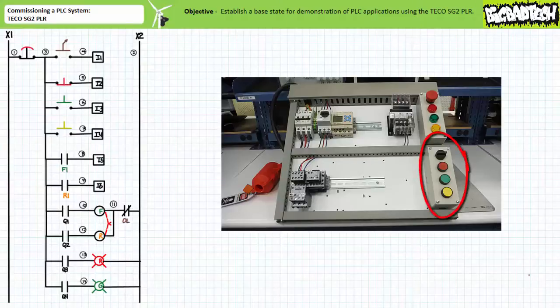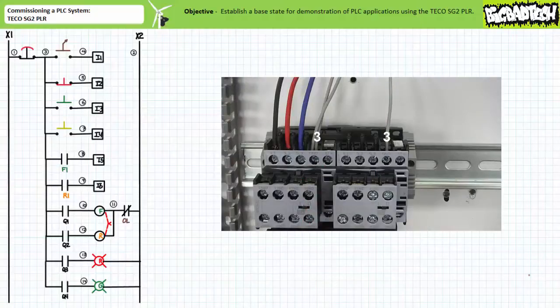The 4 field input devices go in the bottom push button enclosure as indicated in the schematic. Top to bottom, they are the normally open maintained contact selector switch, the normally closed momentary contact red push button, the normally open momentary contact green push button, and finally the normally open momentary contact yellow push button. Alright, let's begin by routing wire 1 from the control transformer output to the normally closed e-stop. Wire 3 then goes from the e-stop to the first 4 field input devices in the bottom push button enclosure. Note the daisy chain connection pools all these devices together. Wire 3 also pools the 1-3 terminals of the F1 and R1 auxiliary contacts.